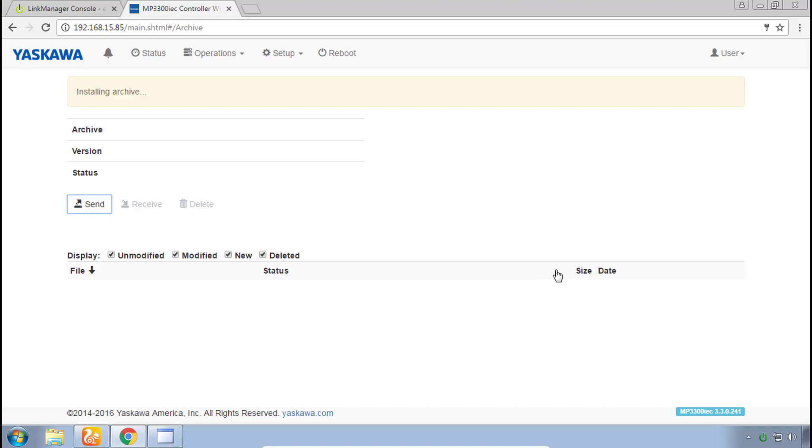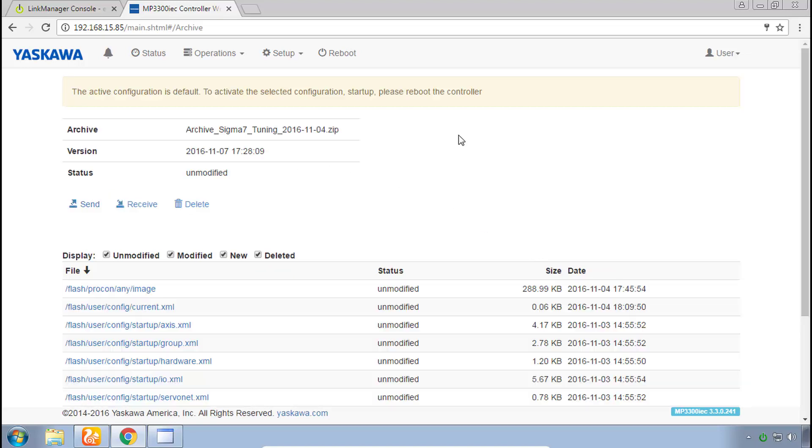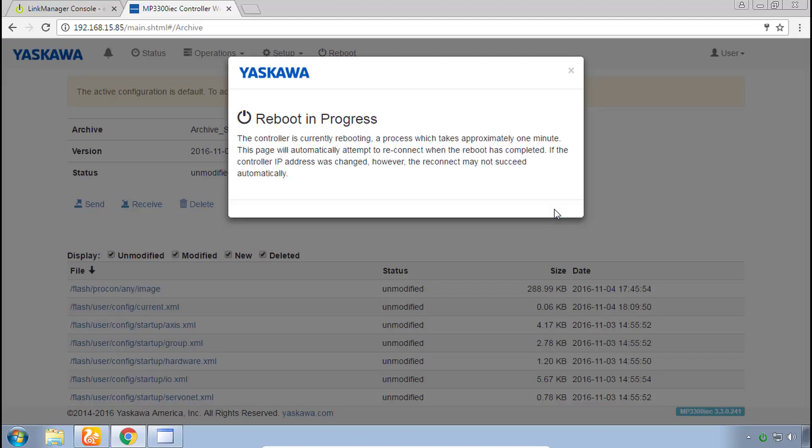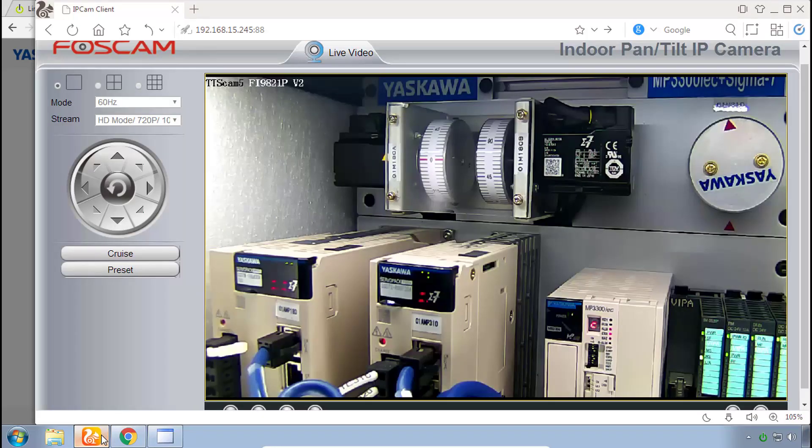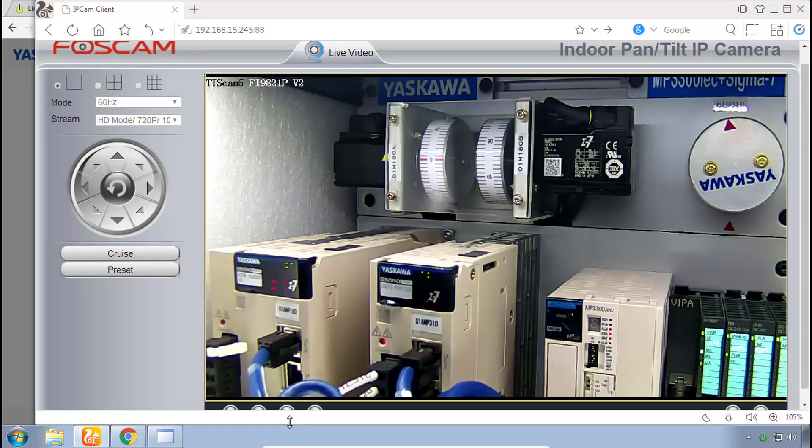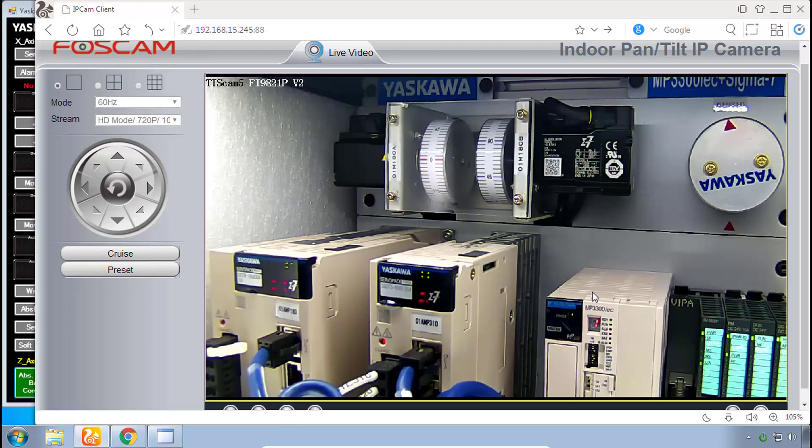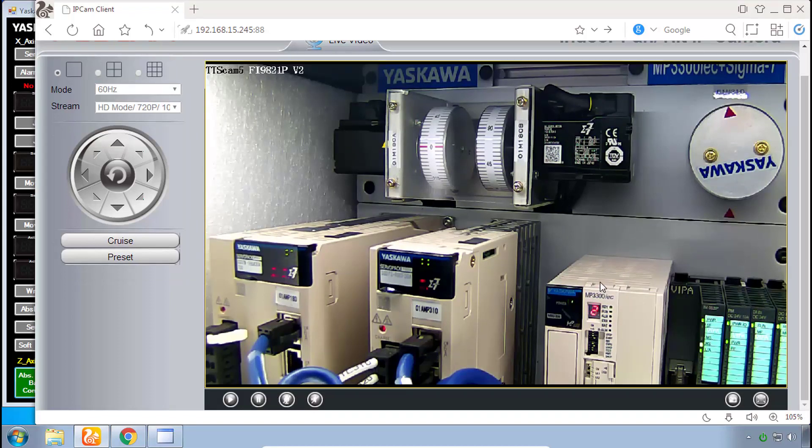The controller says installing archive and now we need to reboot the controller which can be done through this reboot button. Reboot and then confirm again with reboot. This takes about 30 seconds and you can look at the camera in the meantime. When the servos flash off like you see here that means that the system has rebooted. So that put the program onto this controller but we need to send some parameters from this controller over Mechatrolink 3 to each of these amplifiers.